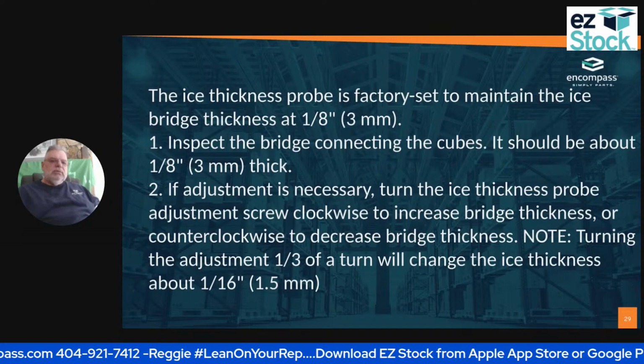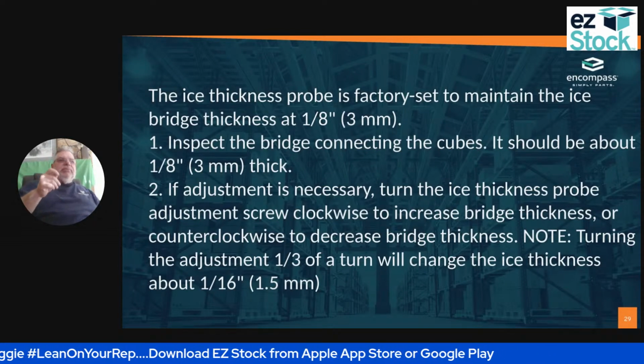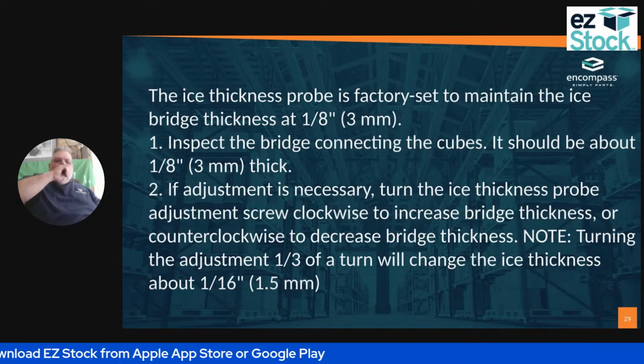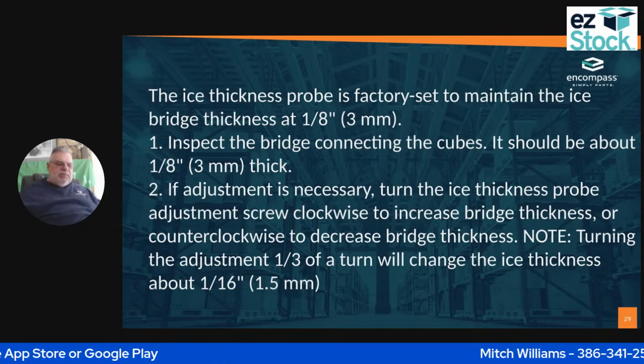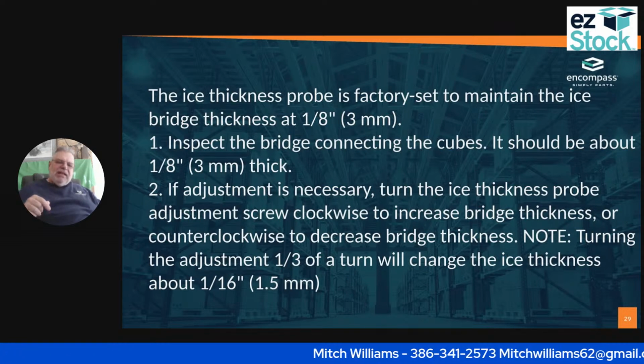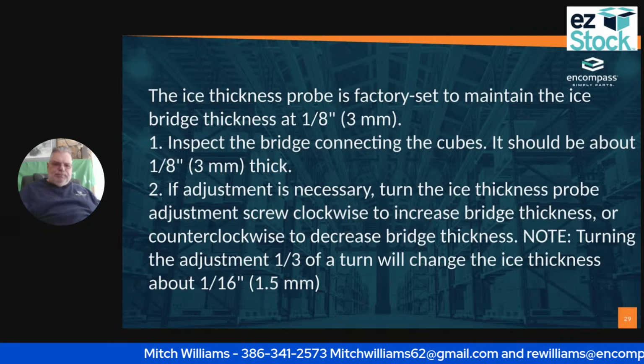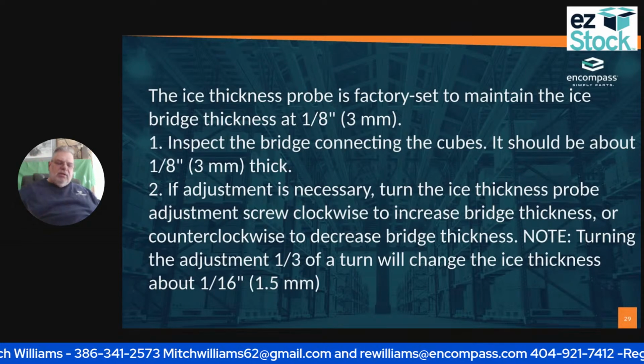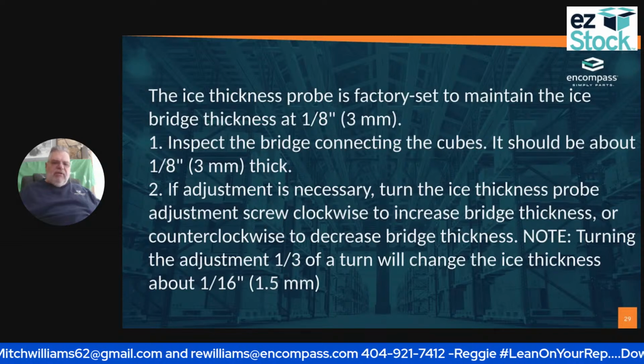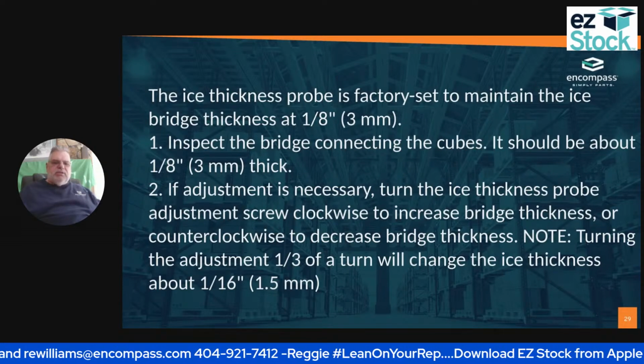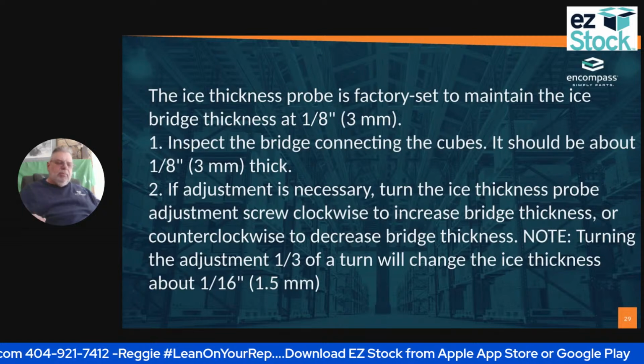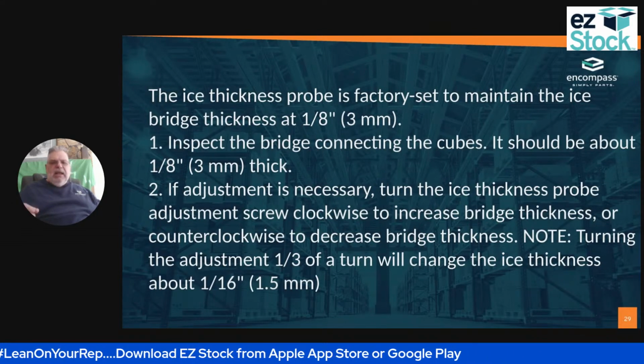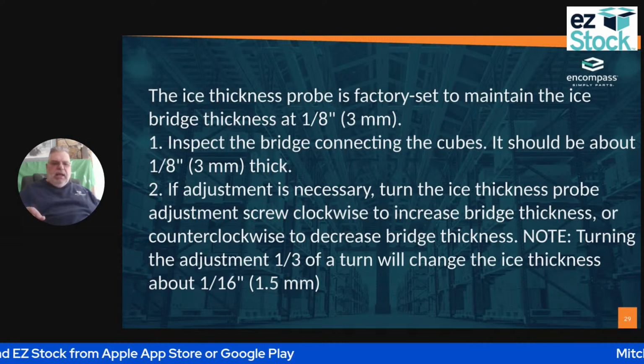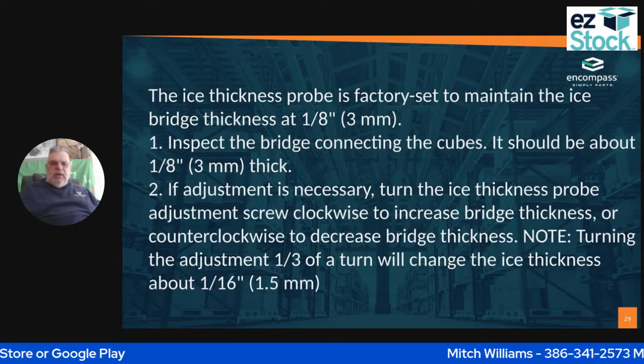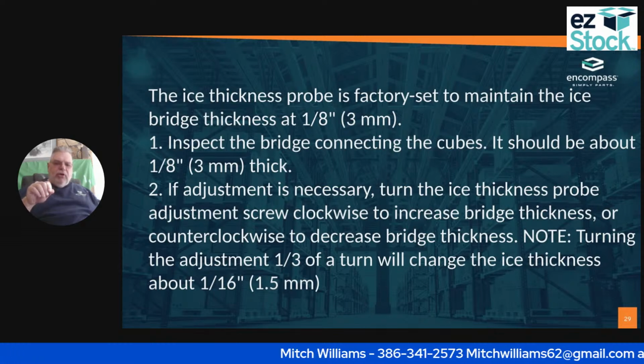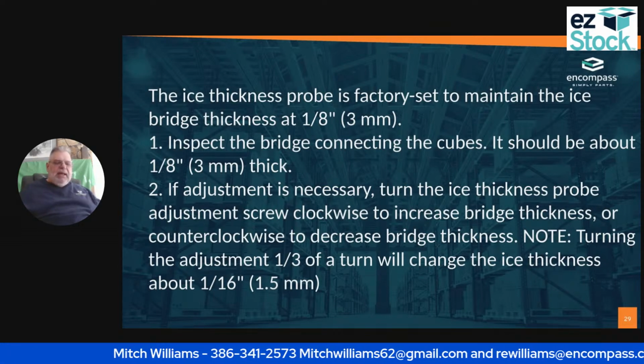Sometimes it gets off a little bit, so I may have to adjust my ice thickness probe. It comes set from the factory at 1/8 of an inch. I check the ice thickness and if I need to adjust it, I can turn the ice thickness probe screws clockwise to increase the bridge, or counterclockwise to decrease the bridge thickness. Turning the adjustment screw 1/3 of a turn will change the ice thickness about 1/16 of an inch.